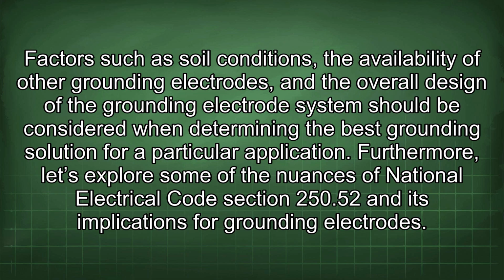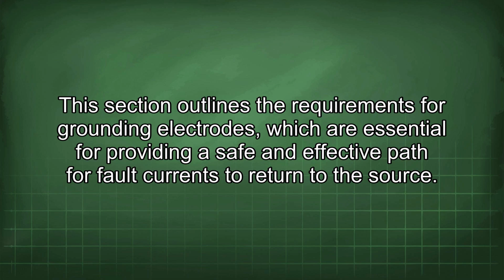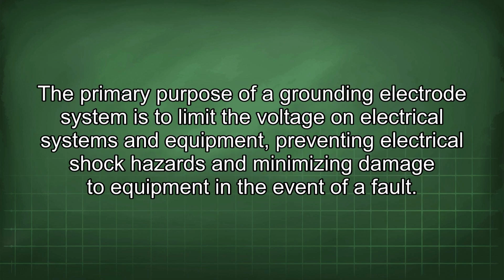Furthermore, let's explore some of the nuances of National Electrical Code Section 250.52 and its implications for grounding electrodes. This section outlines the requirements for grounding electrodes, which are essential for providing a safe and effective path for fault currents to return to the source. The primary purpose of a grounding electrode system is to limit the voltage on electrical systems and equipment, preventing electrical shock hazards and minimizing damage to equipment in the event of a fault.